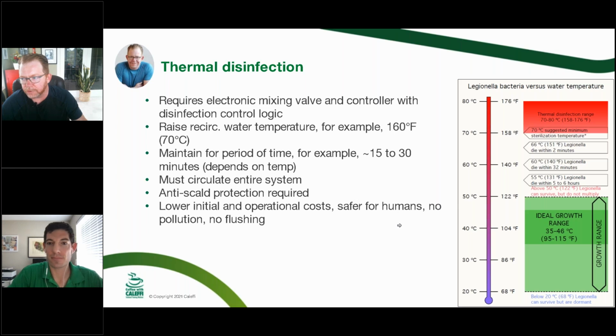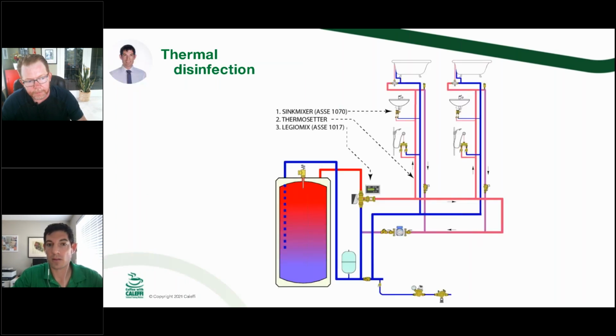So again, just sort of reiterating that point, we have a chart here where we're just sort of outlining again, where Max has got his at 180 degrees, his thermal disinfection time is going to be significantly less. Whereas in my scenario where I'm at 140, 32 minutes. So I was pretty close to what that number would be. So you obviously want to pay attention to that as you're doing the system. And one of the things that is important with that too, and this slide might even be a better way to describe it, is if you're going to do thermal disinfection, you need to verify that temperature all the way back at the end of the recirc loop. So you may be supplying 160 degrees at the outlet of the mixing valve, but if this is some huge school with uninsulated pipes in the basement or something like that, you may still be getting back 120 degrees, and that's not going to cut it.